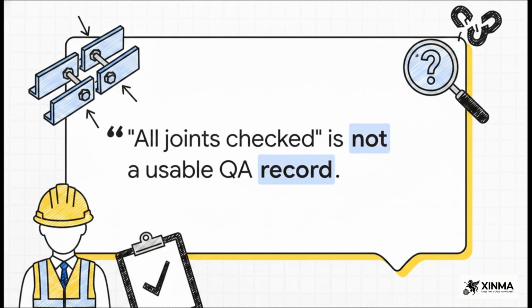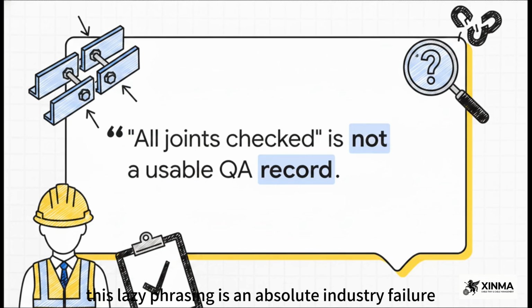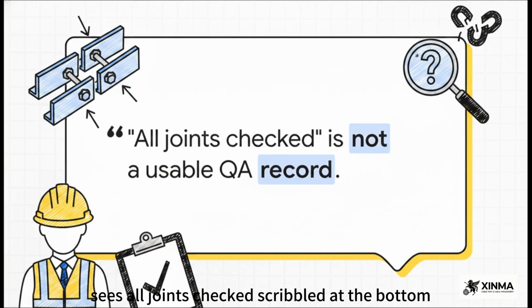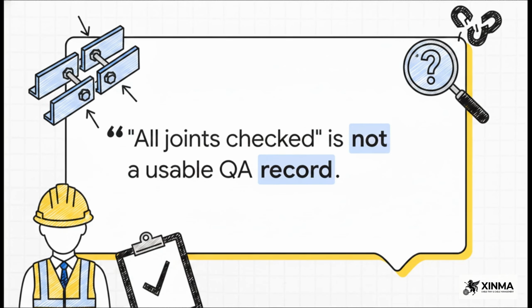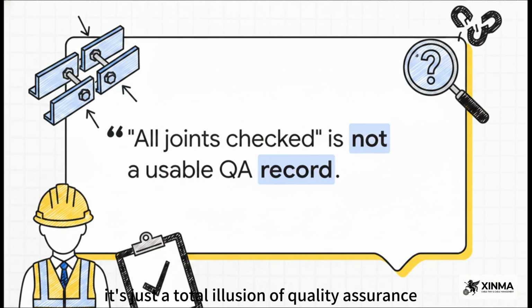All joints checked is not a usable QA record. Let that sink in. This lazy phrasing is an absolute industry failure. When a site manager looks at a clipboard and just sees all joints checked scribbled at the bottom, they know absolutely nothing about the actual safety and integrity of that busway system. It's just a total illusion of quality assurance.